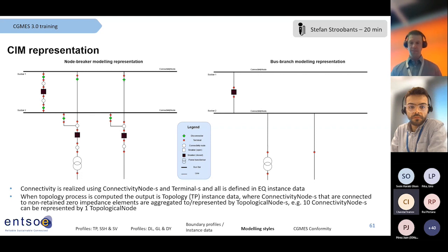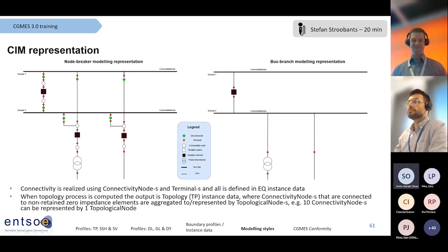There are some workflow nuances that are sometimes hidden from the data exchange. The idea that you can have these virtual breakers doesn't need to be exactly the same as you have in the field, but that is the way to do topology changes. So if you have a remedial action that requires a topology change, rather than having two ways of describing that, we only have one, using those breakers.